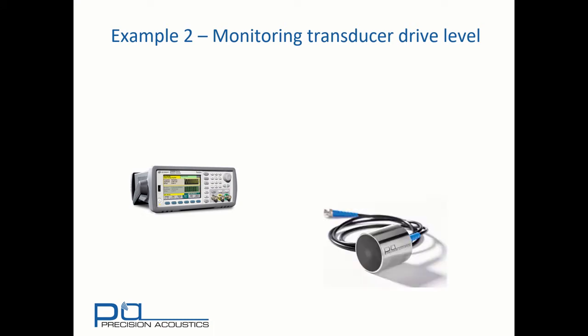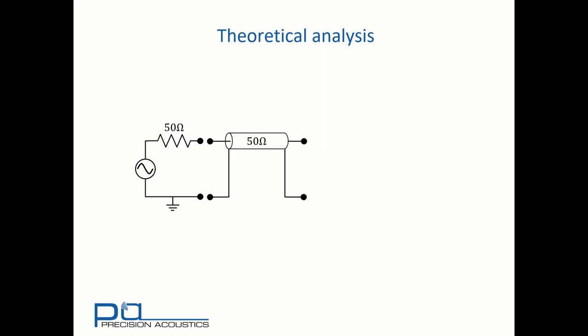Now let's look at another example where we'd like to monitor the transducer drive level. In this case, we have our same function generator, this time with a transducer, and you can see the 50 ohm BNC cable is configured to it. We also have an oscilloscope, and it would be logical to assume that we can simply put a T-piece connecting to the transducer and another cable connecting to the oscilloscope. But let's look carefully at the equivalent circuit for this. We have a function generator with a 50 ohm source that connects via a 50 ohm cable to a transducer — a nicely loaded system.